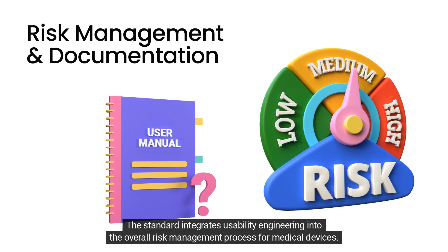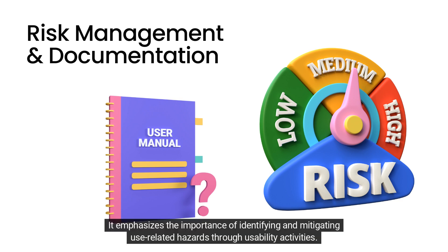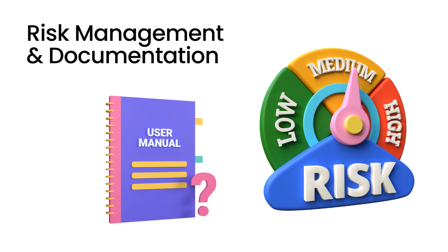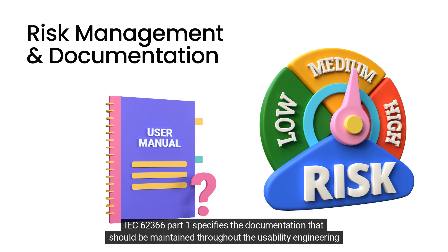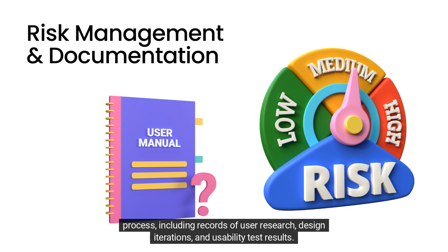The standard integrates usability engineering into the overall risk management process for medical devices. It emphasizes the importance of identifying and mitigating use-related hazards through usability activities. IEC 62366 Part 1 also specifies the documentation that should be maintained throughout the usability engineering process, including records of user research, design iterations, and usability test results.